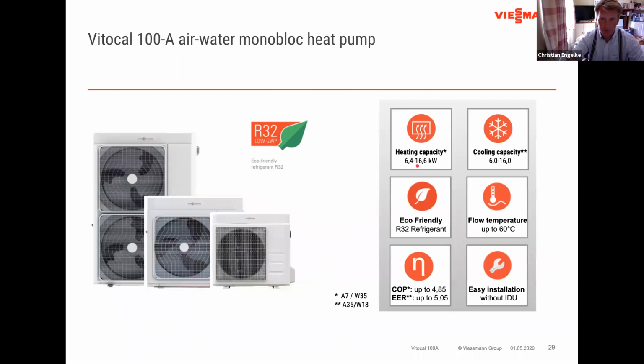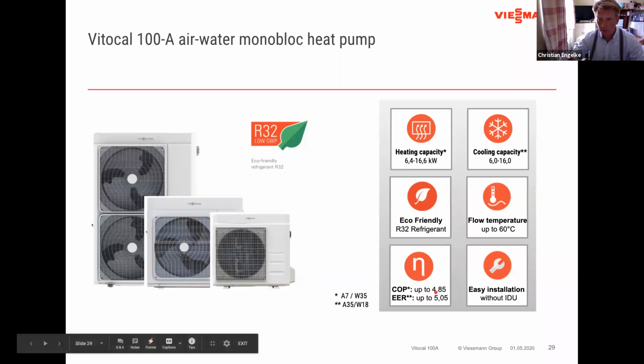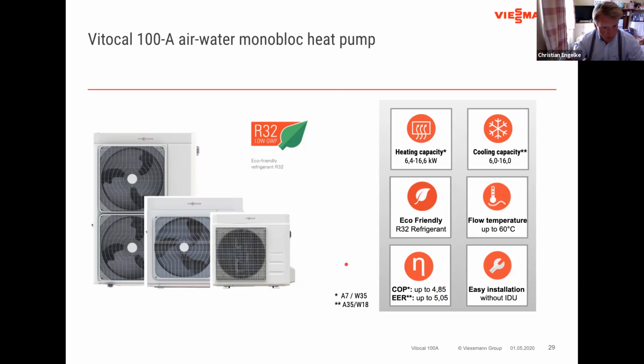So that's the overview. Some benefits or features of this are obviously the new eco-friendly R32 refrigerant gas. And then we have flow temperatures up to 60 degrees. It is also capable of cooling if people like to use it. I have to tell you that the government is not very keen on using the cooling function, but cooling is available. And then we have a high COP efficiency of up to 4.9. And then the easy installation part is because the unit does not come with an indoor unit. So all the components are actually integrated into the outside unit.